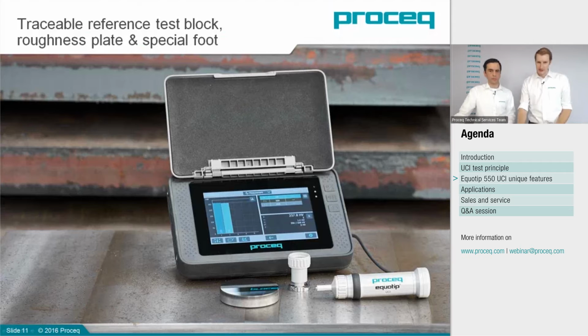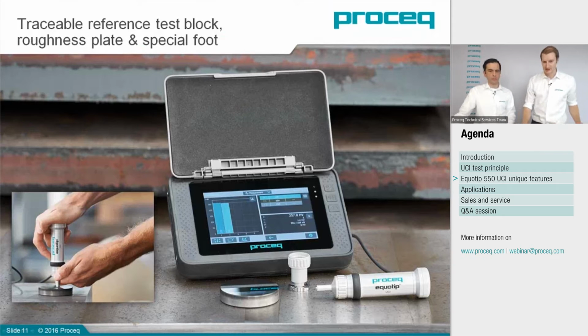Coming to the accessories, as with all our hardness testing solutions, the UCI probe comes with a traceable reference test block. Prior to each hardness test, you should verify your instrument on a traceable test block to make sure it is working properly and showing correct values. Such a test block is shipped with all our units.